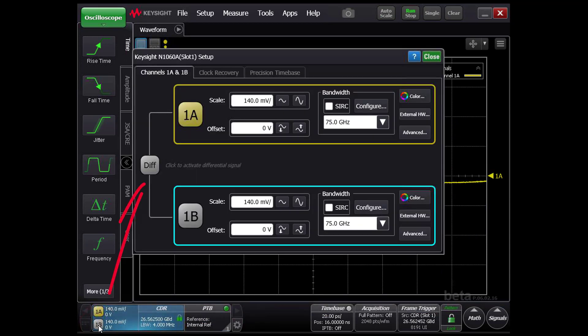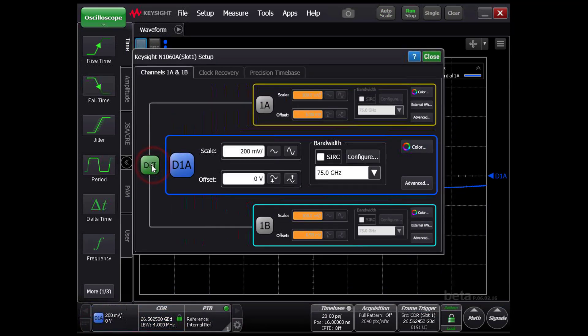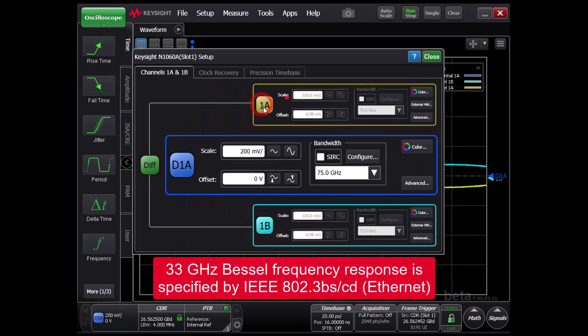We will turn on the differential signal and set up the receiver for a 33 gigahertz Bessel response.